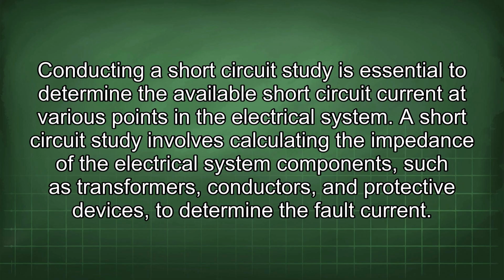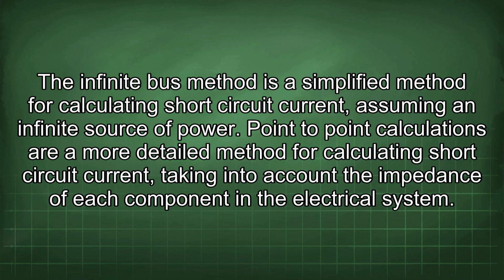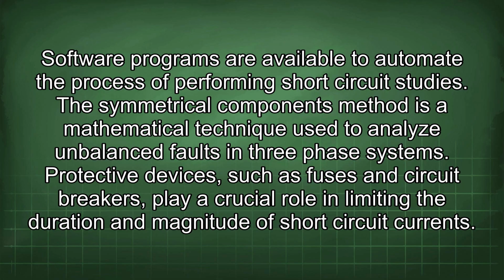Conducting a short-circuit study is essential to determine the available short-circuit current at various points in the electrical system. A short-circuit study involves calculating the impedance of the electrical system components, such as transformers, conductors, and protective devices, to determine the fault current. The infinite bus method is a simplified method for calculating short-circuit current, assuming an infinite source of power. Point-to-point calculations are a more detailed method for calculating short-circuit current, taking into account the impedance of each component in the electrical system. Software programs are available to automate the process of performing short-circuit studies. The symmetrical components method is a mathematical technique used to analyze unbalanced faults in three-phase systems.